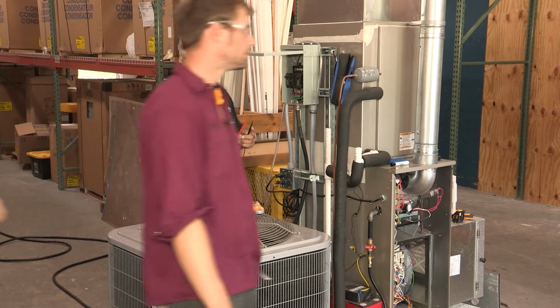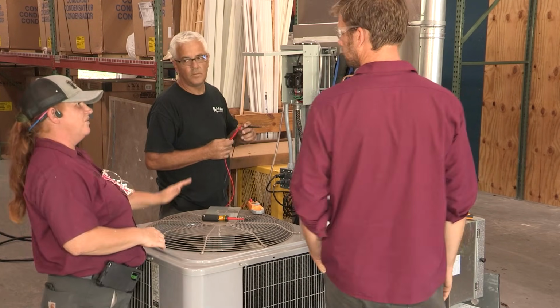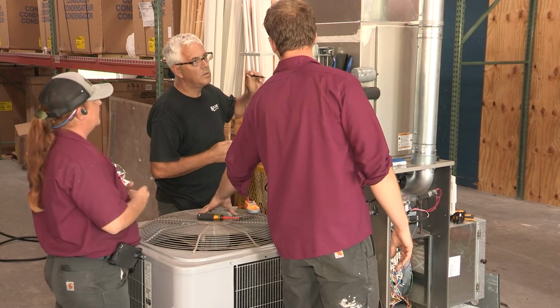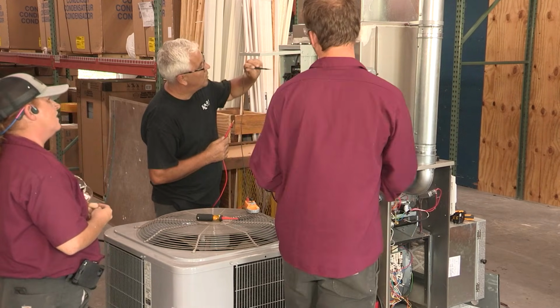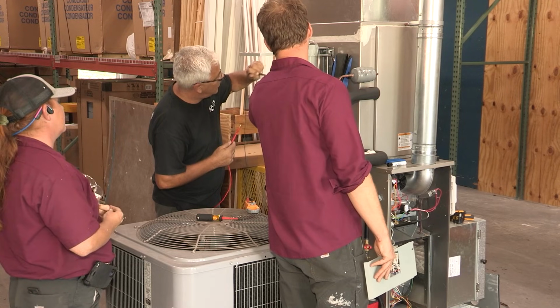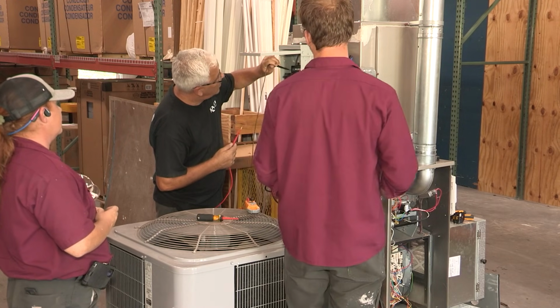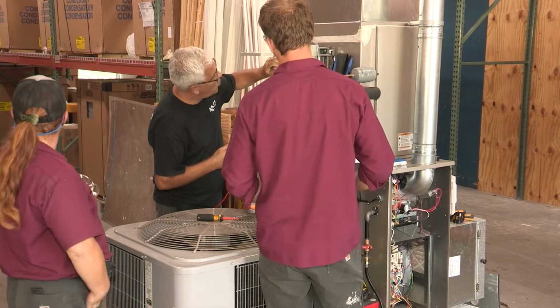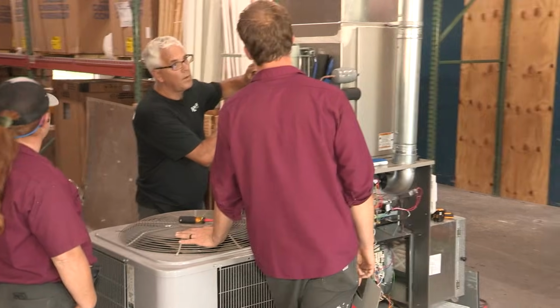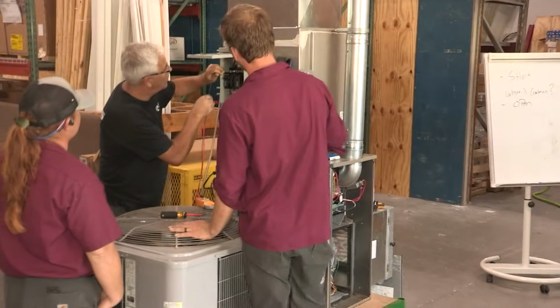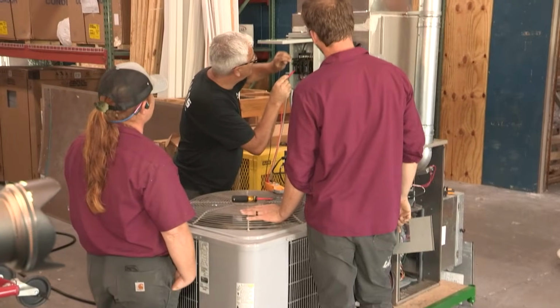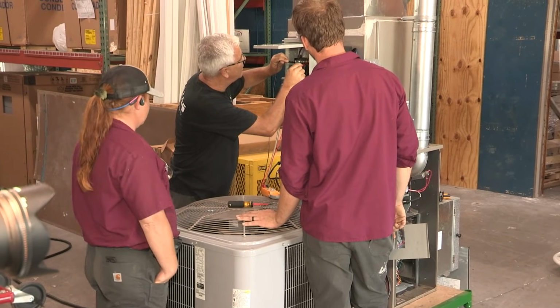So you need a new breaker. No, a new main breaker for the house? Yeah, that would be commonly that you would check the main breaker, and if you weren't getting it there, it would be an issue with the meter or power supply to the home. To check one leg at a time, then you would go to ground. Then you would go to neutral, which would be most accurate there, instead of ground to the box.